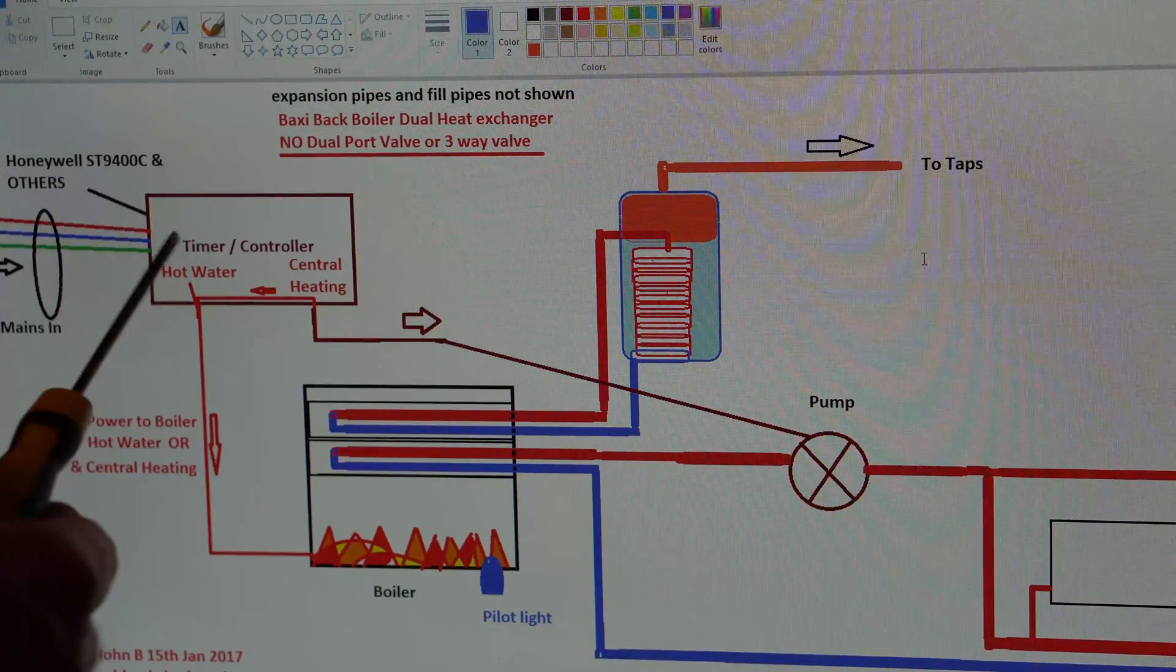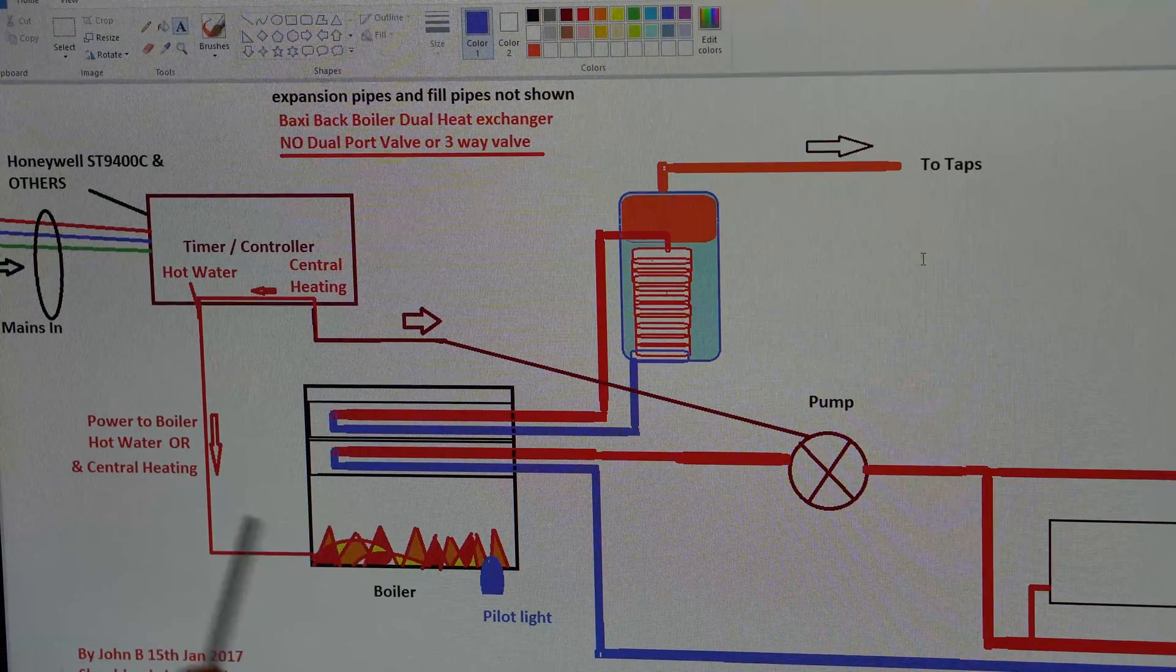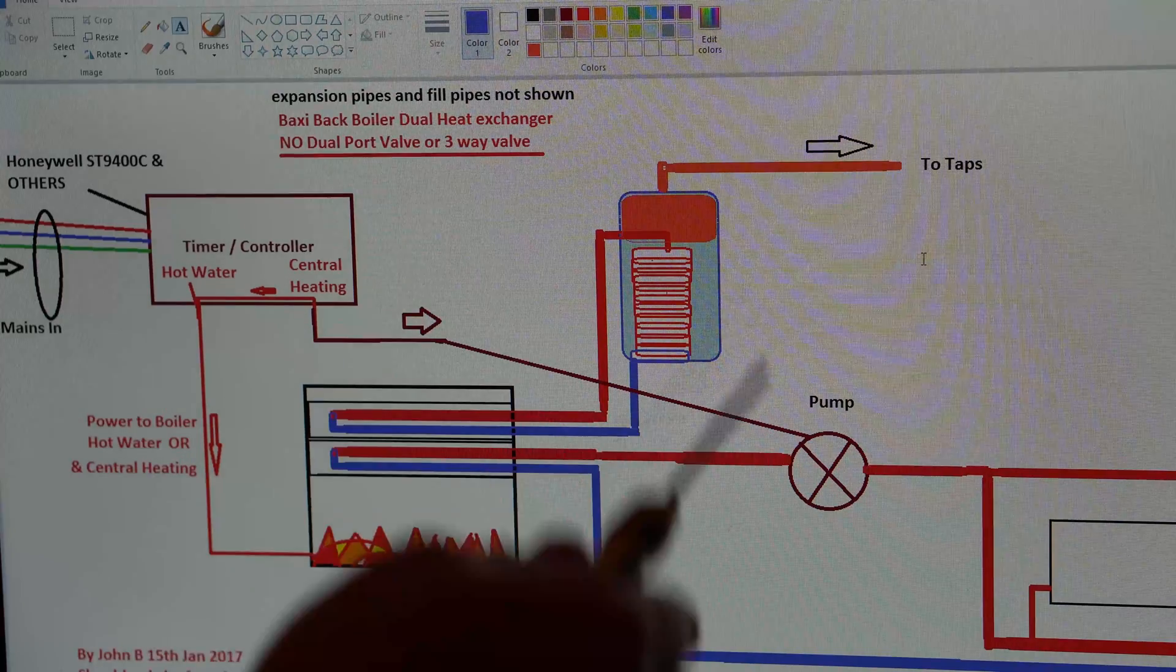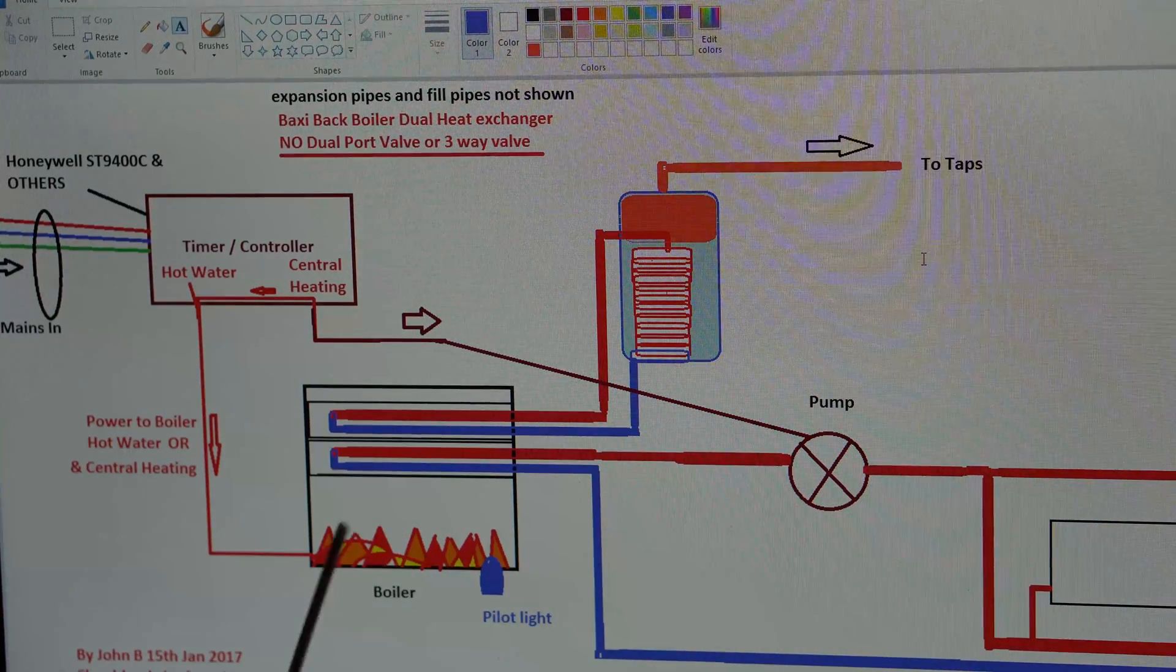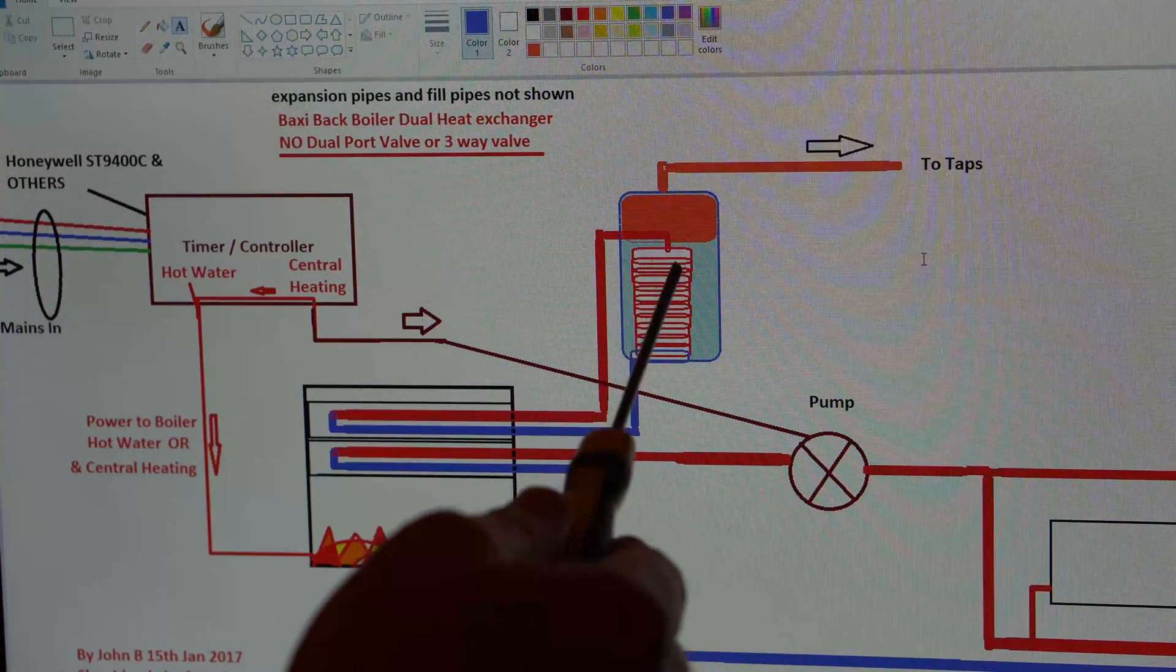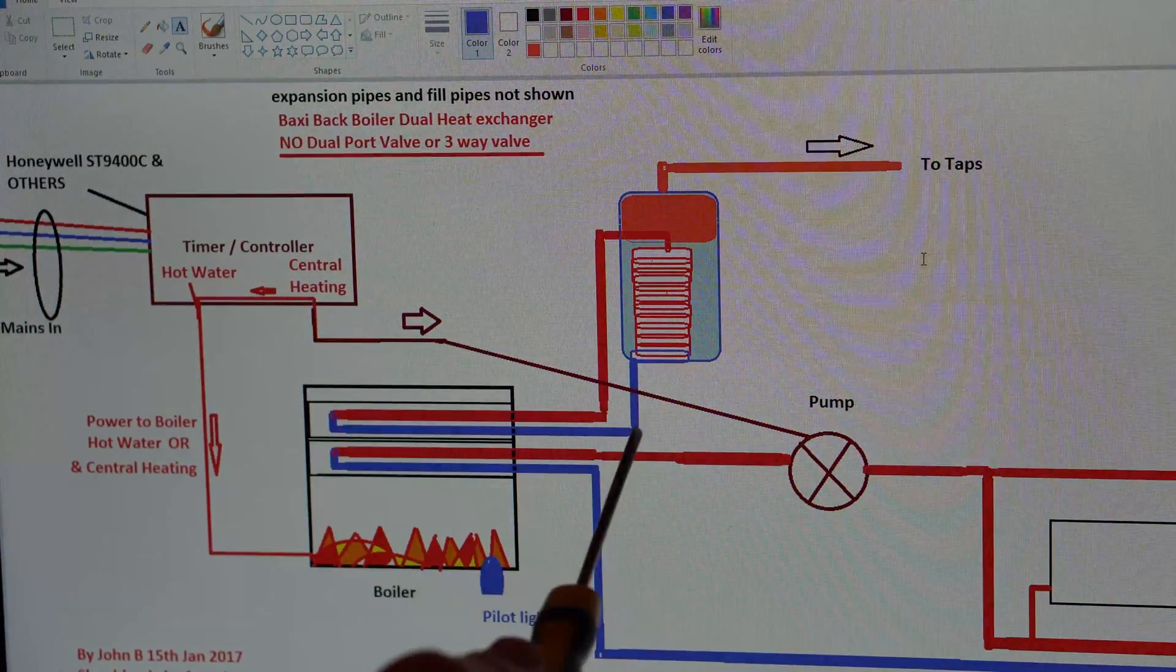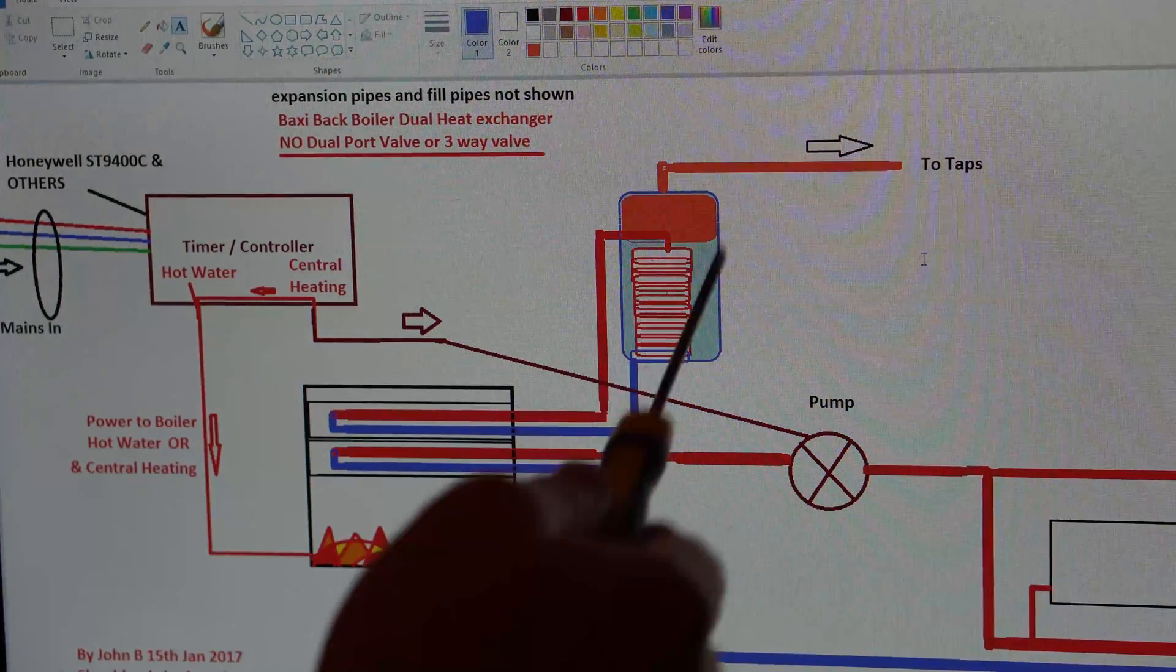Power goes into the timer. When you demand hot water, it just turns on the boiler. Nothing else. One of the relays turns on, powers up the boiler. And this is a gravity-fed system. There are two heat exchangers. Flame is heating up the water in this heat exchanger. Hot water rises, heats the water in the tank via this coil, and then the water sinks and returns back, heated up again. So that's the hot water system.